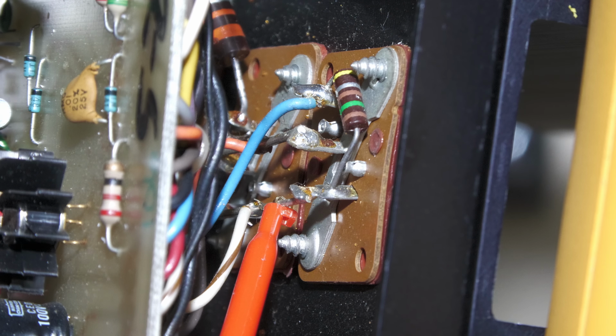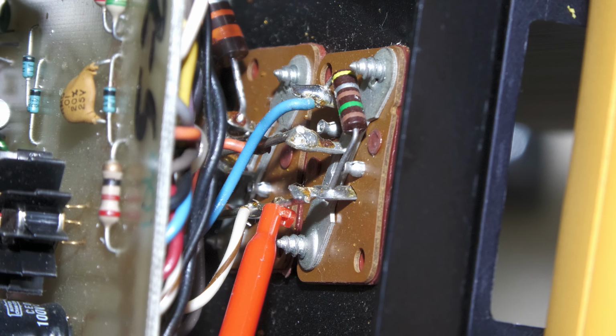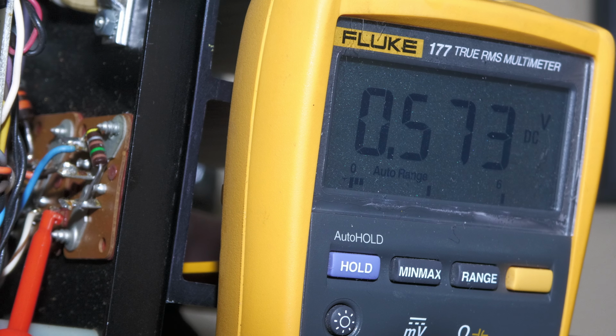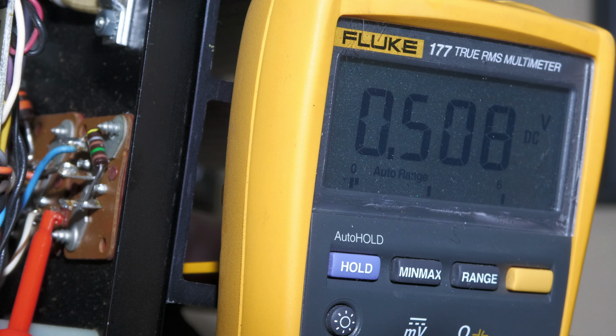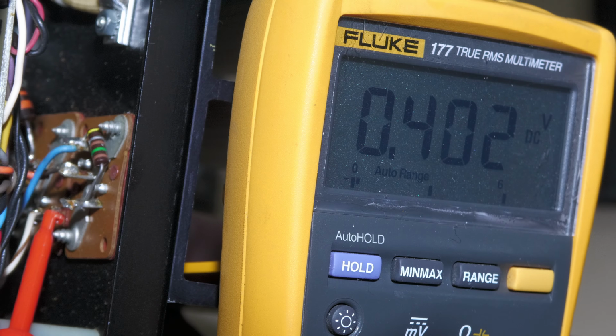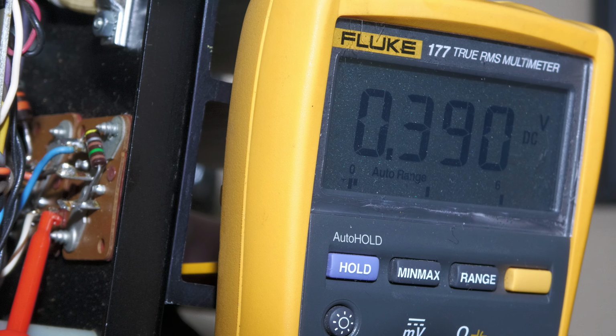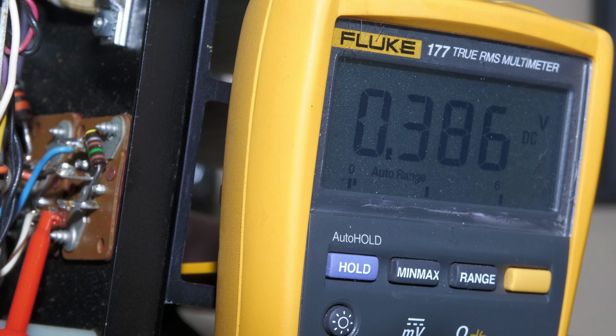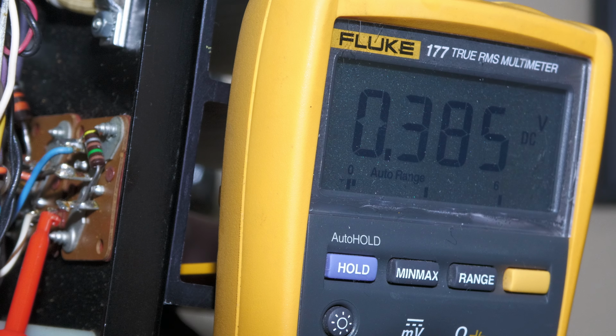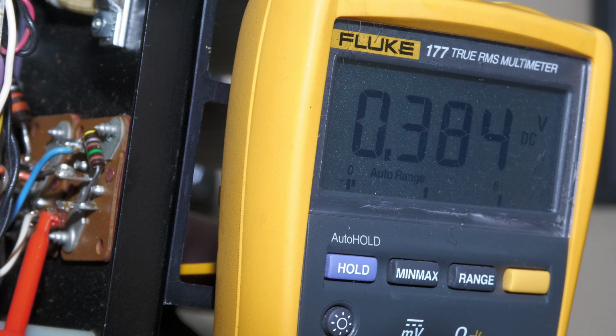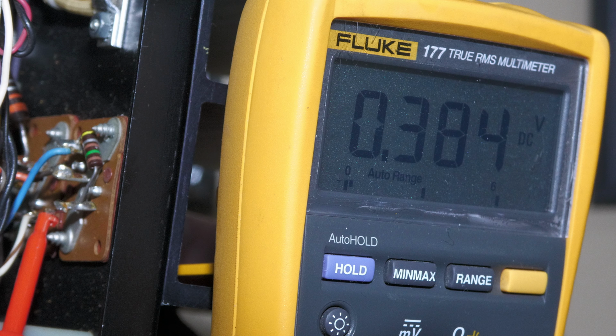Now we are set up and connected to the right channel to look at and set bias. As you can see, we're also over 500 mV. Let's bring that down near 380. We will leave it at 384 mV. Again, per the service manual, the spec is plus or minus 100 mV, and we are only a few millivolts off. The bias is now set.